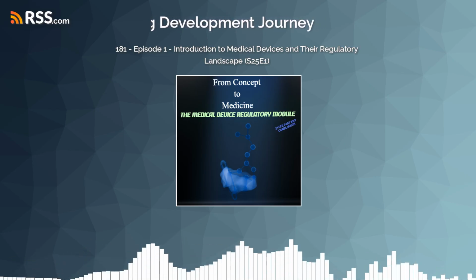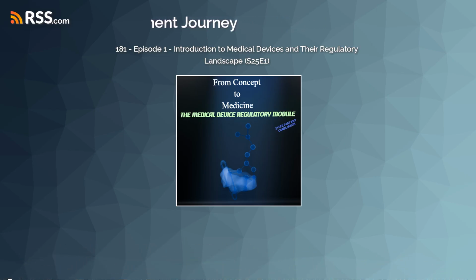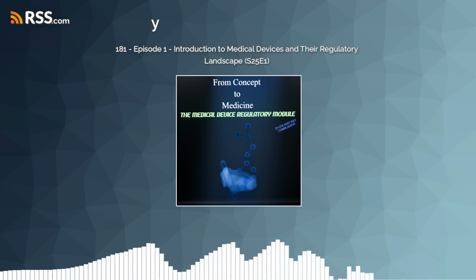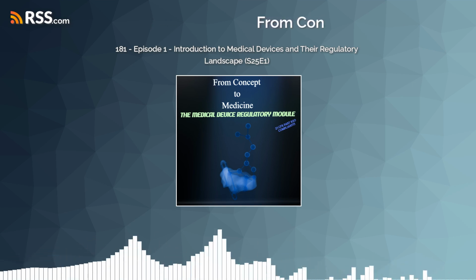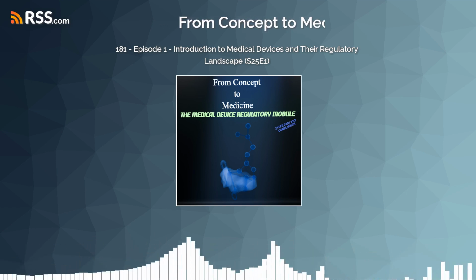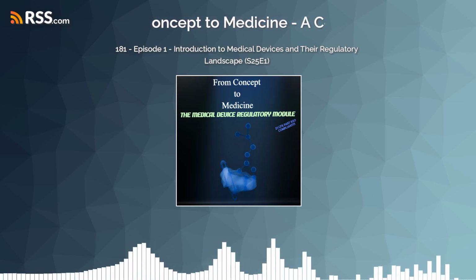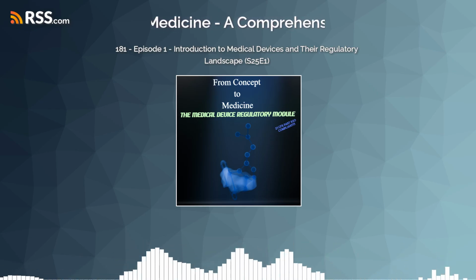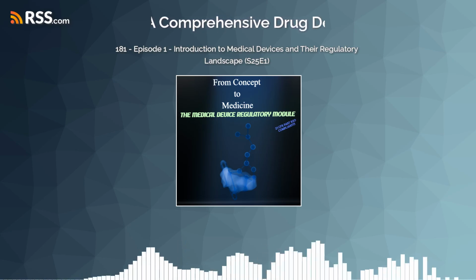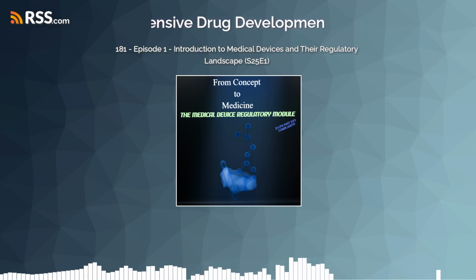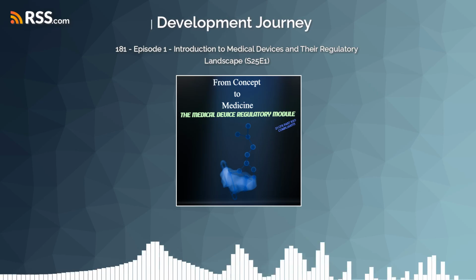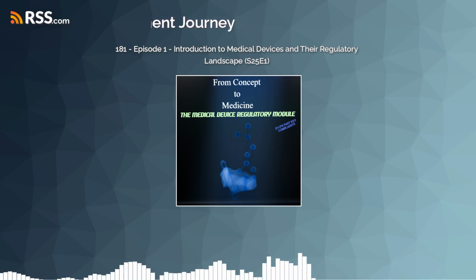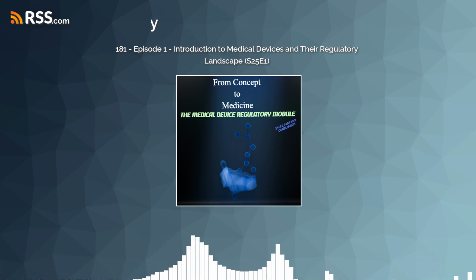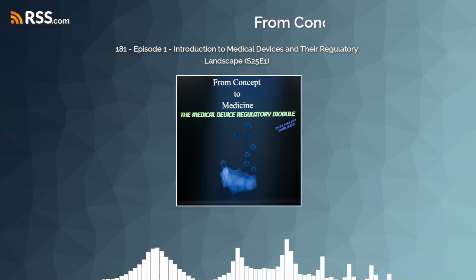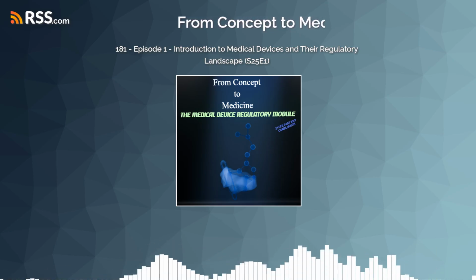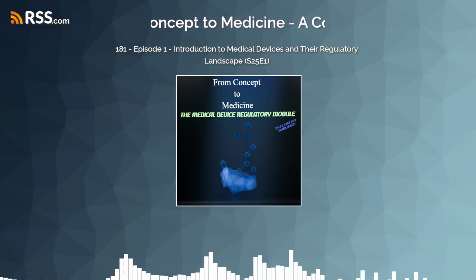Okay, now what about the top tier, Class 3? These are the highest risk, right? What kind of devices are we talking about here, and what scrutiny do they face? Correct. Class 3 devices pose the highest potential risk to patients. These are typically devices that are life-sustaining, life-supporting, or are implanted devices. Or they could just present a potential unreasonable risk of illness or injury. For these, general controls and even special controls are simply insufficient. They require the most rigorous level of regulatory review.